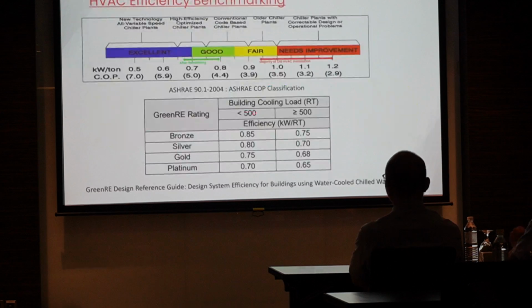Some benchmarks: typically for air conditioning systems we follow the ASHRAE standards. Based on ASHRAE, good is 0.7 to 0.85 kilowatt per RT, fair is 0.85 to 1 kilowatt per RT. So far in Malaysia, most plants, maybe 15 to 20 years old, are looking at 1 kilowatt per RT and above. ASHRAE recommends retrofitting to improve the system and bring it down lower. The current target is around 0.65 to 0.75 kilowatt per RT.